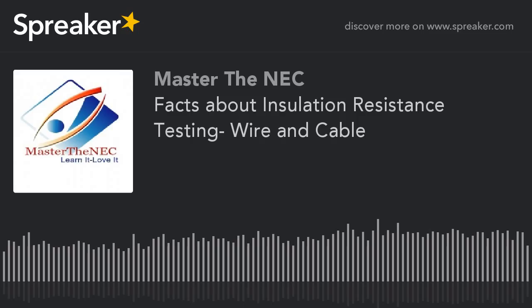And the reality is we're not doing the manufacturers of those products a real justice, because those products have a specific test need. I've used them in my career for motors, testing windings, a lot of things like that, to test the reliability of the insulation over time if it's deteriorated, or older type of equipment or motors, and that's a very viable need. If I've got cables that have that intimate contact with some type of armor with the insulated conductor, then I have a viable test product here. So really just trying to dispel the myths here, because I routinely get people testing insulated conductor to insulated conductor and they're trying to interpret these results, and I'm like, really, it's not what you should be doing.